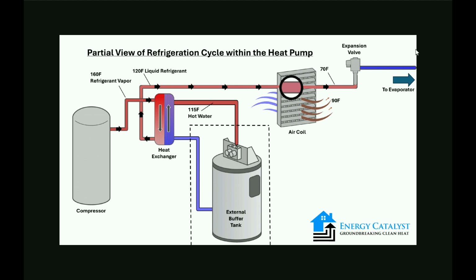each other. That is actually the exact reason why, as you make higher and higher temperatures with a refrigeration system, the efficiency continuously drops, right? That's just the laws of physics. And it's for this very reason, because the more that refrigerant gets hotter and hotter, the more that it's going to be fighting against itself on the back end, on the evaporator side.